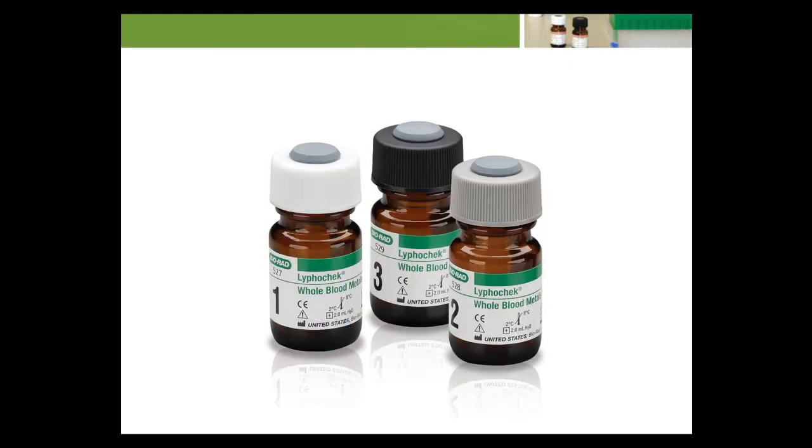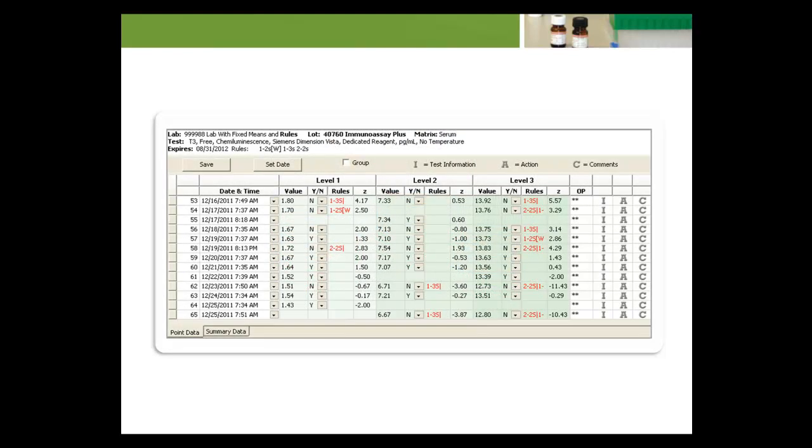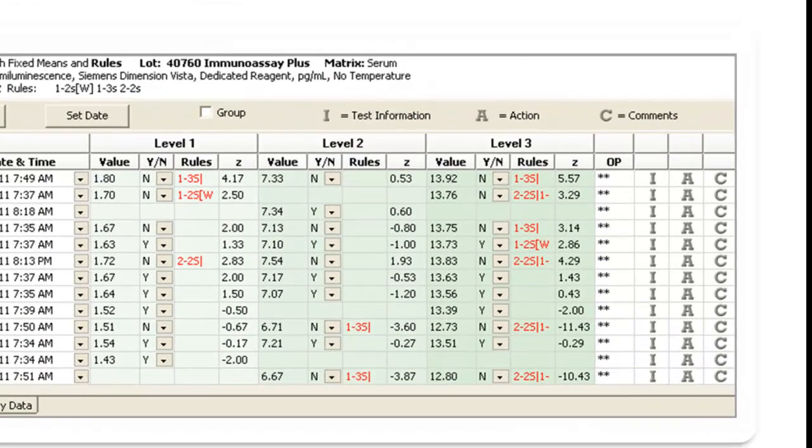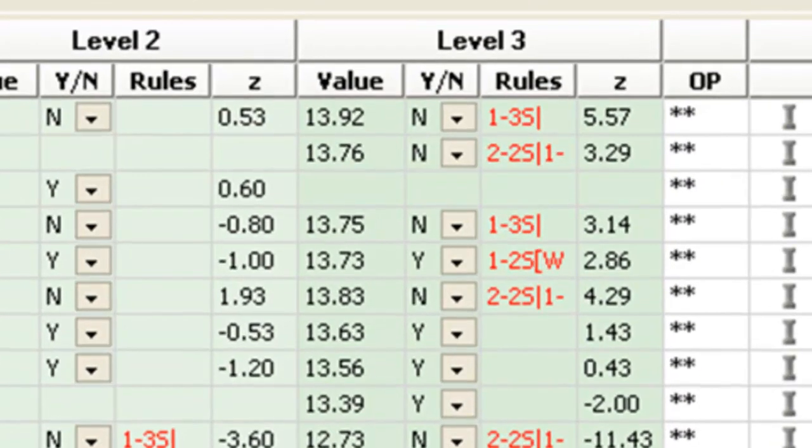The primary tool used by laboratories to perform routine QC is the periodic testing of QC specimens, which are manufactured to provide a stable analyte concentration with a long shelf life. A laboratory establishes the target concentrations and analytic imprecision for the analytes in the control specimen assayed on their instruments. Thereafter, the laboratory periodically tests the control specimens and applies QC rules to the control specimen results to make a decision about whether the instrument is operating as intended or whether an out-of-control error condition has occurred.